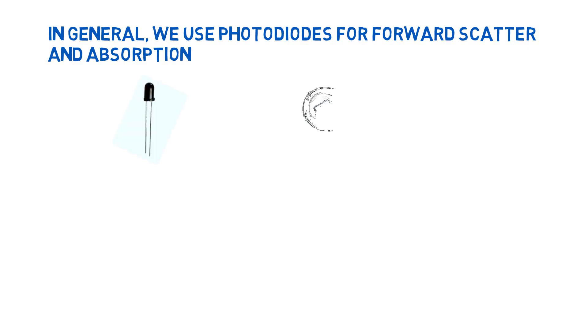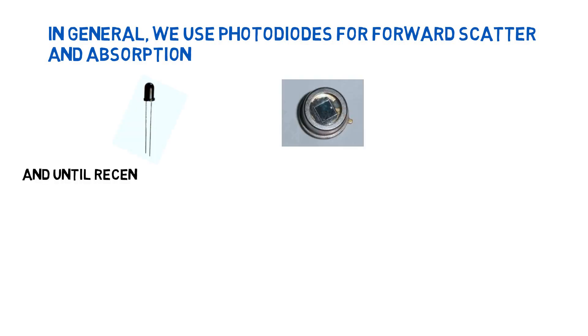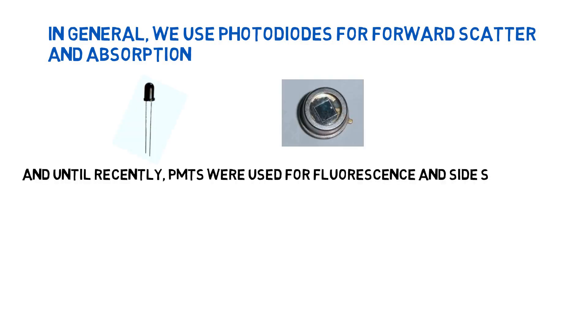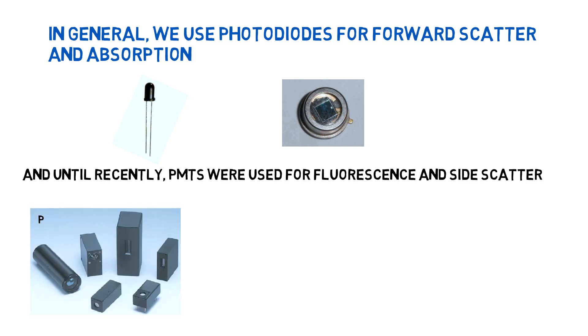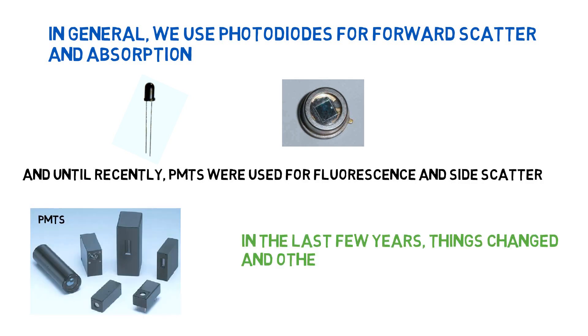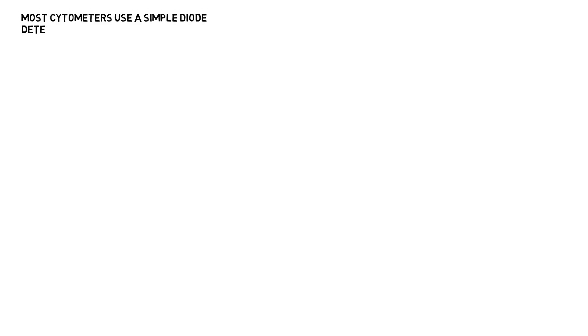In general, we use photodiodes for forward scatter and absorption. And until recently, PMTs were used for fluorescence and side scatter. But in the last few years, things changed, and other detectors are being used.